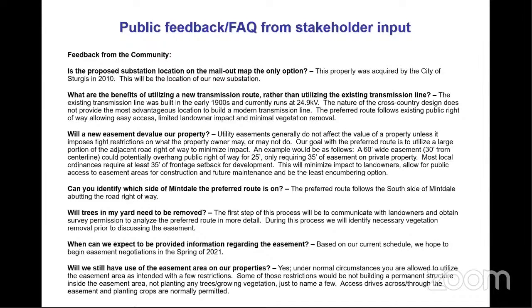So will we still have use of our easement area on our properties? The answer is yes. Under normal circumstances, you're allowed to utilize the easement area as intended, with a few restrictions, and those restrictions are always called out in the easement agreement. Some of those restrictions may be not being able to build a permanent structure inside the easement area, or not planting trees or growing vegetation there. The reason we do this is that when we design this transmission line, we have to follow NESC clearances, which are engineering guidelines for safety that we must follow.